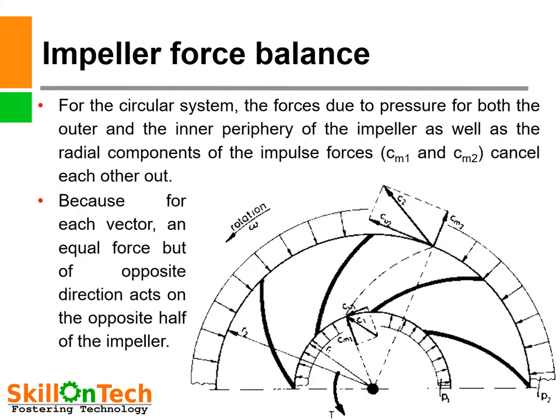Impeller force balance. You can see a picture of the impeller and how forces are balanced. For the circular system, the forces due to the pressure for both the outer and the inner periphery of the impeller, as well as the radial components of the impulse forces CM1 and CM2, cancel each other out — because for each vector an equal force but of opposite direction acts on the opposite half of the impeller. So these forces cancel each other and the impeller force is balanced.